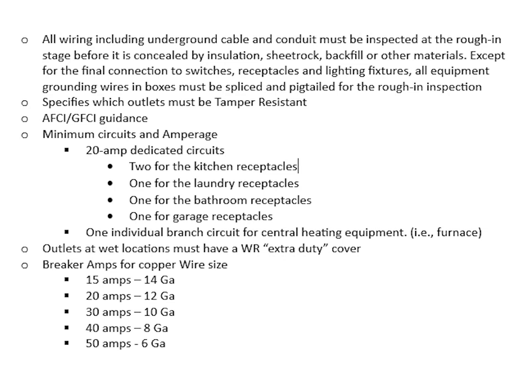Minnesota gives a great 7-page guide that highlights relevant code. The link is in the comments. Some entries in the guide. All wiring, including underground cable and conduit, must be inspected at the rough-in stage before it is concealed by insulation, sheetrock, backfill, or other materials. Except for the final connection to switches, receptacles, and lighting fixtures, all equipment grounding wires in boxes must be spliced and pigtailed for the rough-in inspection.